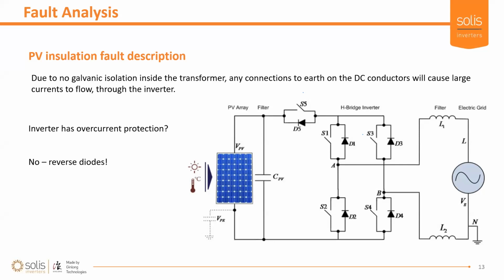You can even short the output of the inverter and it will survive that. It's got short circuit protection. However, due to the reverse diodes in the IGBTs, so if you look at both diode 1 and 3, those will go into forward biased mode if you have a positive voltage relative to earth on the live. So if your L on the grid is higher than your neutral, which it's quite 50% of the time it is, which is connected to earth, you will see that those will go into forward bias mode and there will be a lot of current flowing through. So even if those switches opened up fast enough, which they do, because we've tested short circuit protection, a lot of current still flows through the diode, which is very little resistance, which causes a lot of current and a lot of damage.